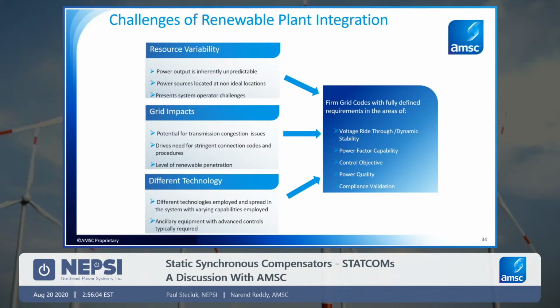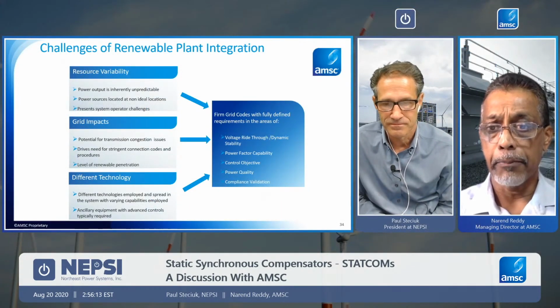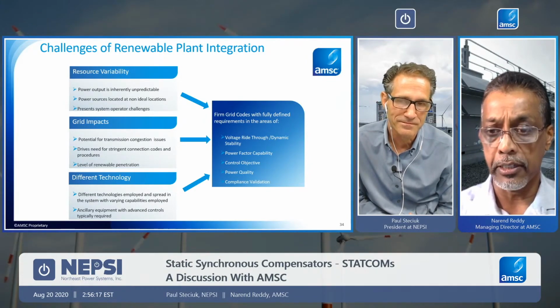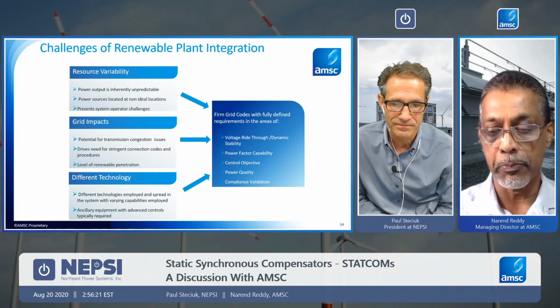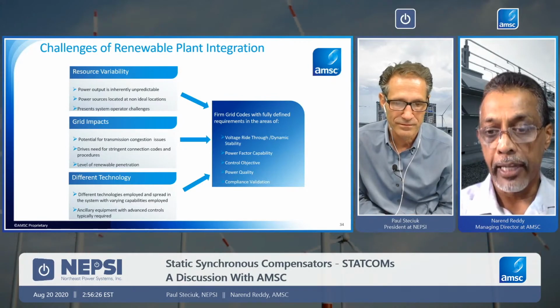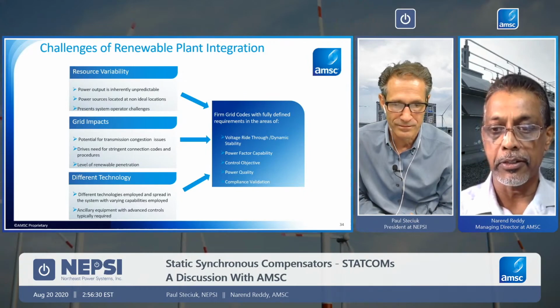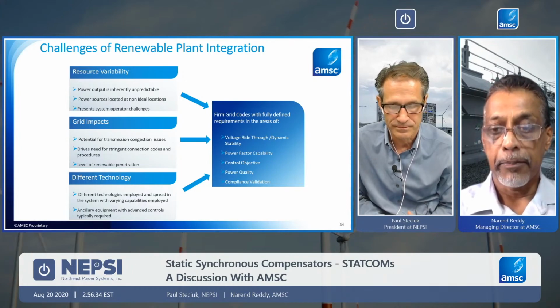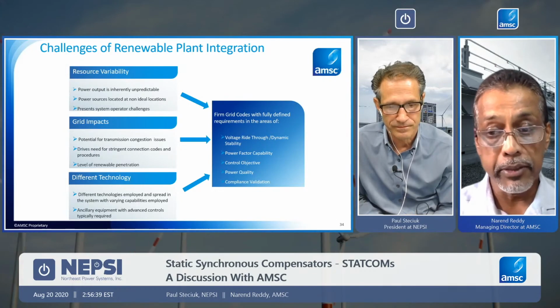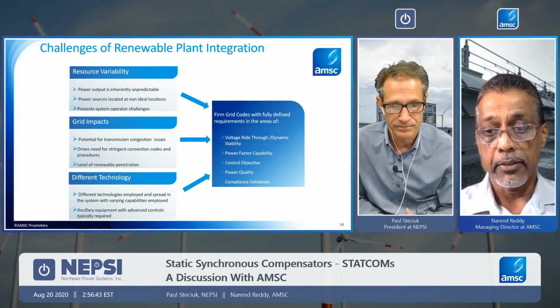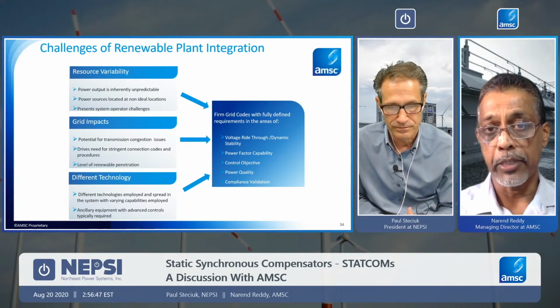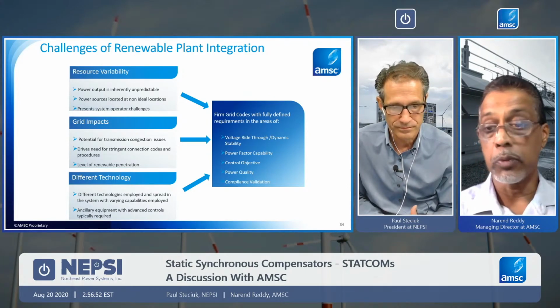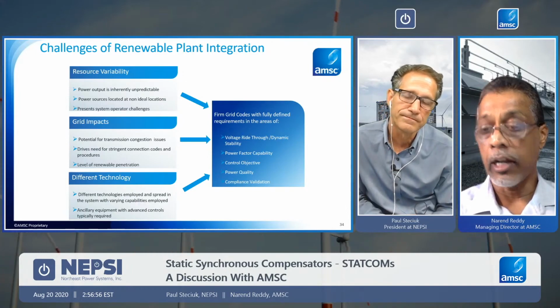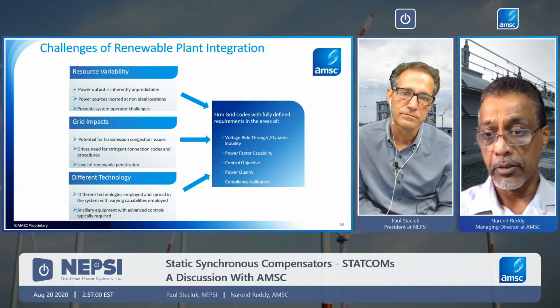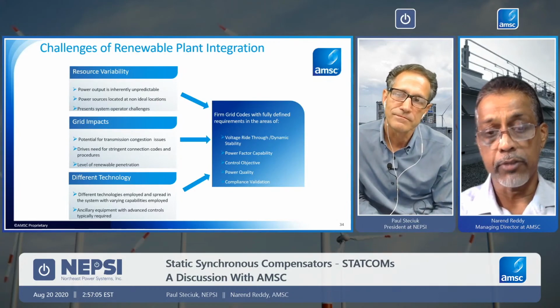So that variability does present operator challenges because from a grid operator or a utility perspective, a renewable plant is really considered as just any other power plant. In terms of comparing to a synchronous thermal power plant, behavior is expected to be the same, because the grid or the consumers are relying on that power to be provided. Obviously, these renewable plants may not be going into the strongest parts of the grid, and so weak grid conditions could apply. The impact of the renewable variable generation at a certain part of the grid might be more pronounced than other places. And so how much renewable energy we are putting into the grid at a point really affects how the grid would react, whether that amount of power can be evacuated or not.